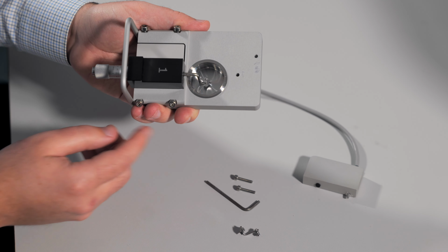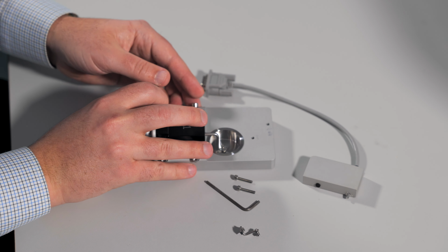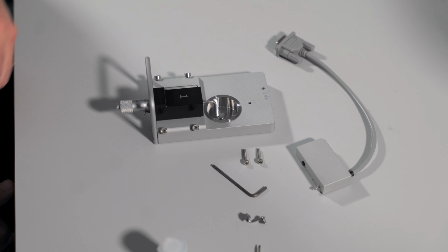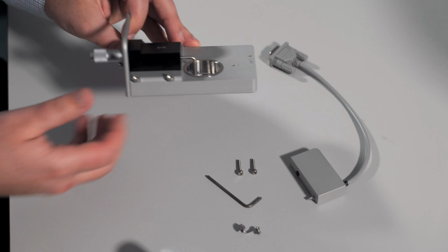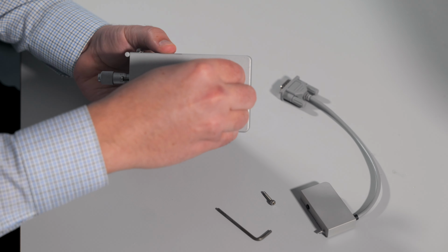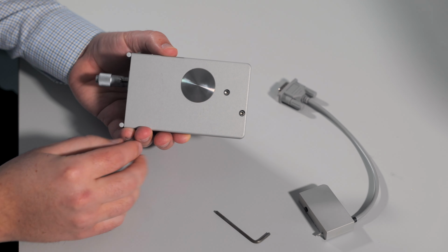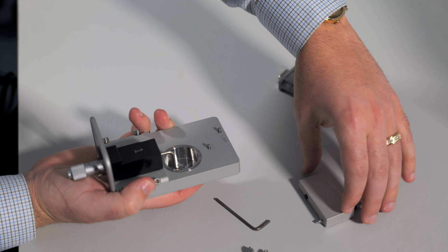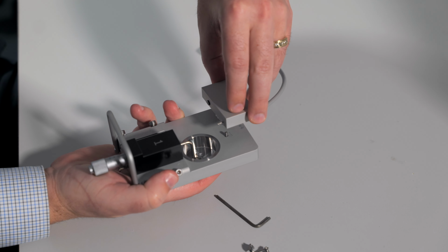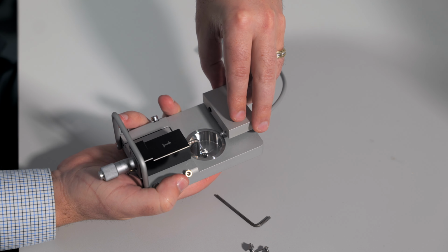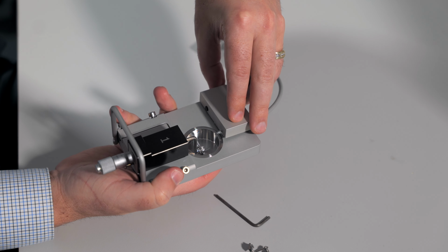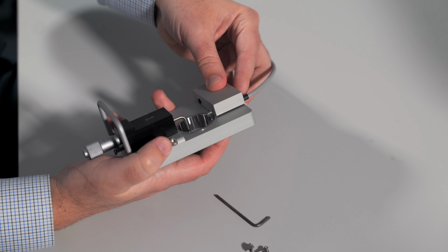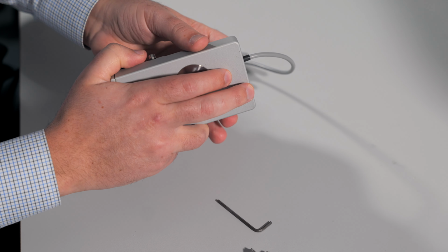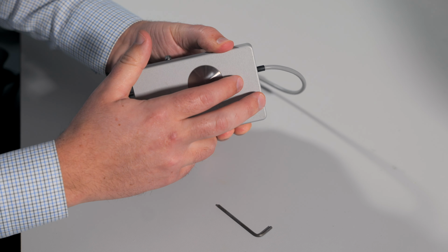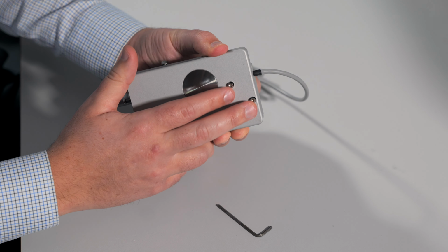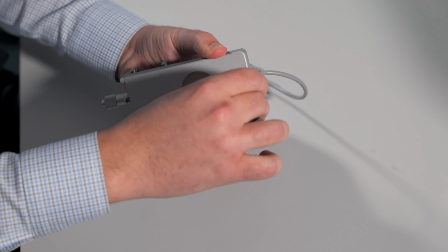You can now add the replacement transducer. In order to add the replacement transducer, take your chamber, flip it over, and add the 2 screws in the bottom. You will hold these in place and take your replacement transducer, line it up along the edges of the chamber, and set it in place. You will feel the 2 screws on the bottom start to push against you. Hold the transducer in place and take your Allen key to secure the screws.